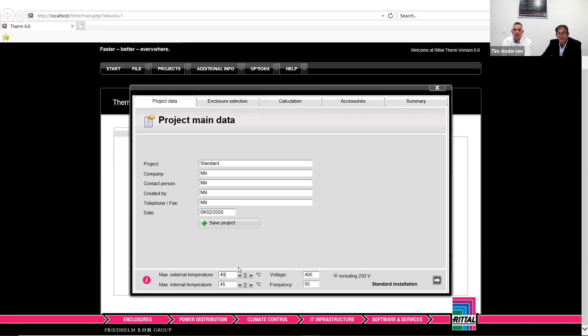So I'm going to flick over now to the enclosure selection. I've inputted these two variables, and now we're looking at what sort of enclosure we have. We're going to pick a Rittal enclosure called the TS, which is a standard industrial range with a pretty good IP rating. I've picked a standard size here - 2 meters high, 800 mil wide, and 600 mil deep.